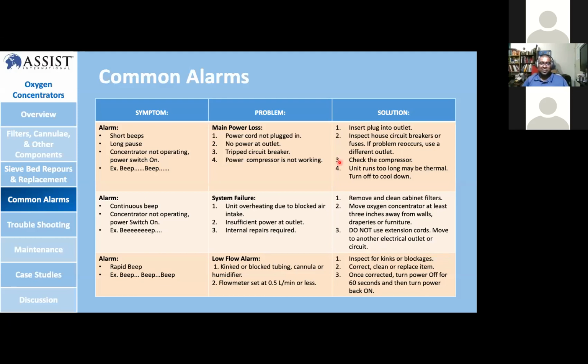Common alarms. These are the interesting part of it. With most oxygen concentrators, I have seen that you get an oxygen concentrator with an alarm, but eventually you end up not doing troubleshooting and instead remove the alarm cable. So that's not so good. Always remember, when you get an alarm, start to find out the reason for the alarm. And for most of the alarms, you can go to the user manual, like a short beep, you can refer to the manual. At the same time, if you get a short beep, long noise, or pulse, and the oxygen concentrator is not operating, make sure the power is checked, like maybe you have a power loss. Insert the power and check by using a multimeter whether you have voltage or not.